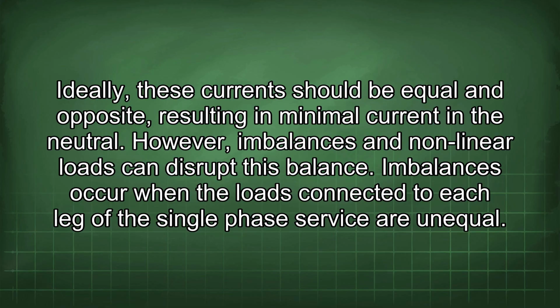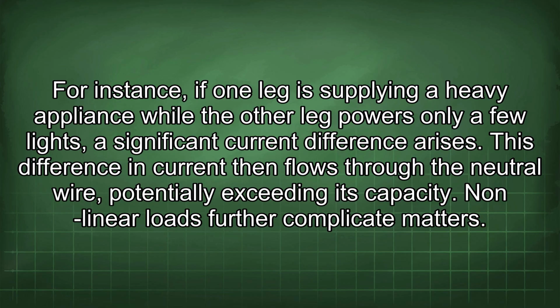Imbalances occur when the loads connected to each leg of the single-phase service are unequal. For instance, if one leg is supplying a heavy appliance while the other leg powers only a few lights, a significant current difference arises. This difference in current then flows through the neutral wire, potentially exceeding its capacity.